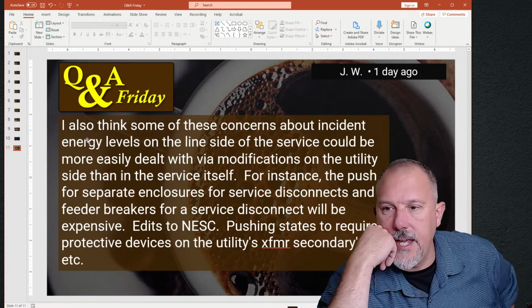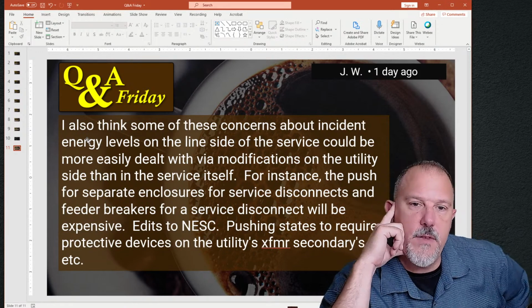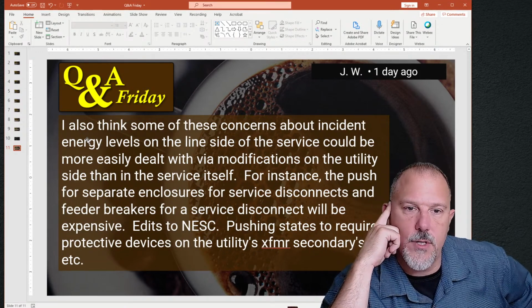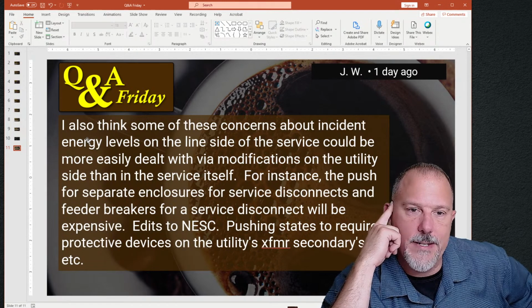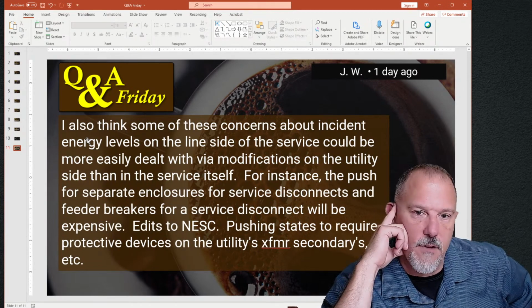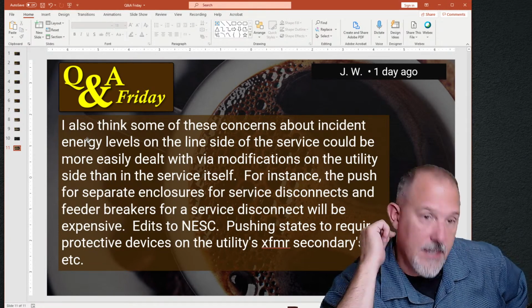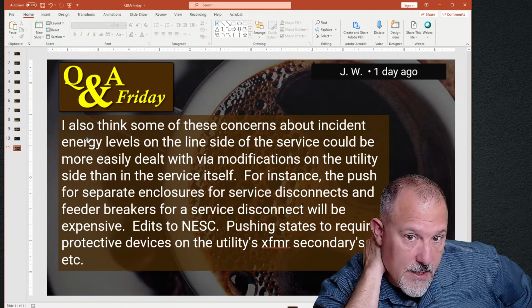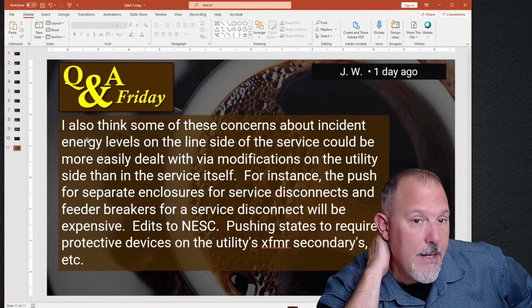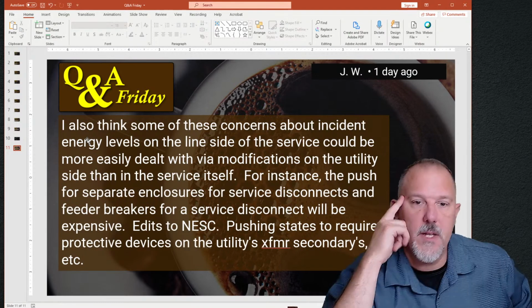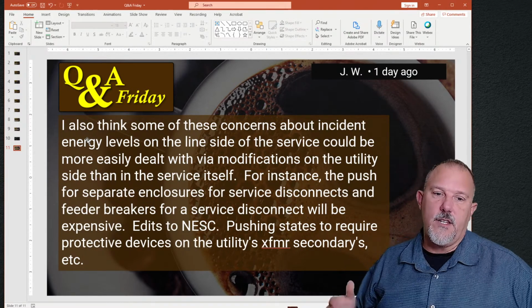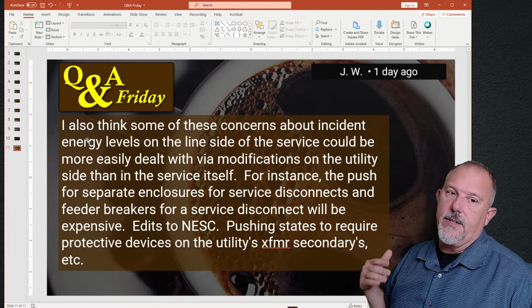I also think, hey, you're welcome, Alejandro, I also think some of these concerns about incident energy levels on the line side of the service could be more easily dealt with via modifications on the utility side than in the service itself. For instance, the push for separate enclosures for service disconnects and feeder breakers for a service disconnect will be expensive. Edits to NESC. Pushing states to require protective devices on the utility's transformer secondary, etc.